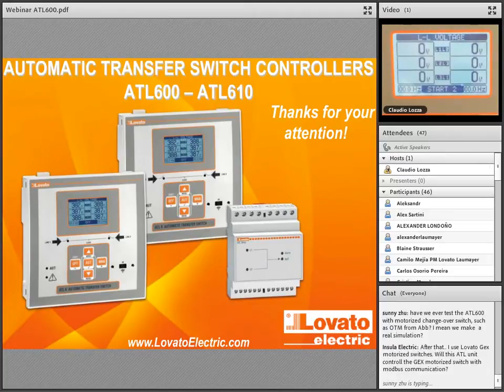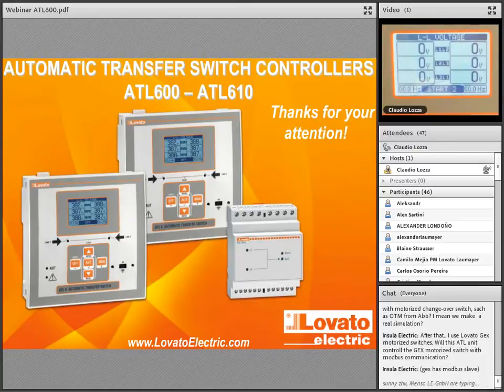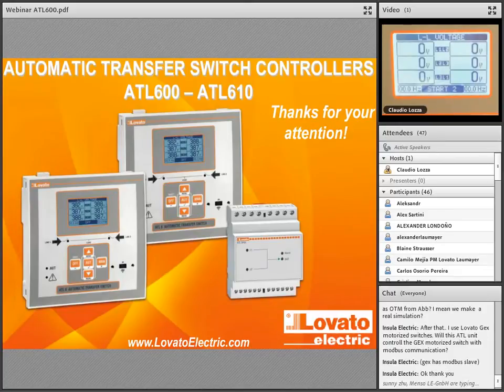Insula Electric asked: I use the Lovato GEX motorized switch. Will this ATL unit control the GEX motorized switch with Modbus communication? The ATL can't communicate with other devices for control. It can be used in supervision, but can't control the switch through Modbus. You can only use the digital output and digital input for feedback, to control the switches.